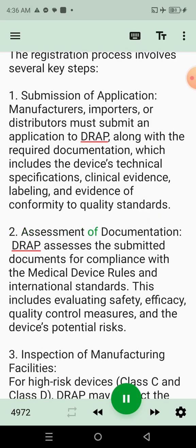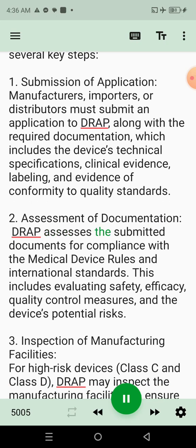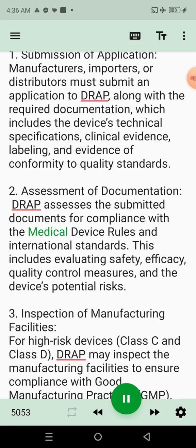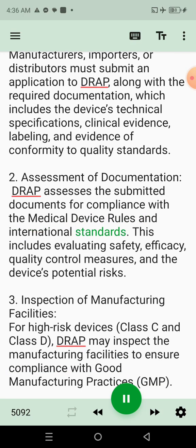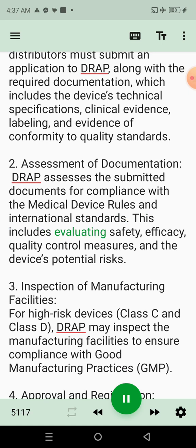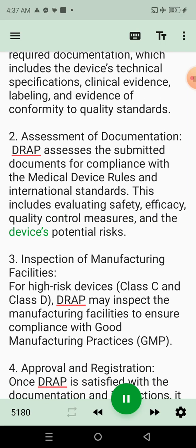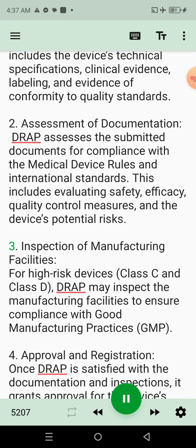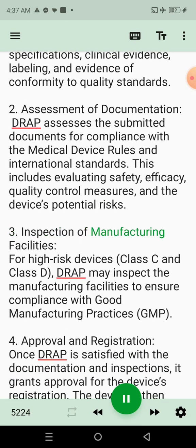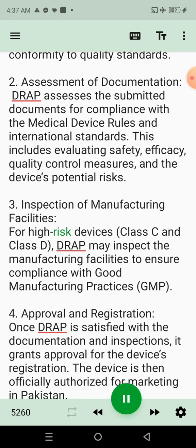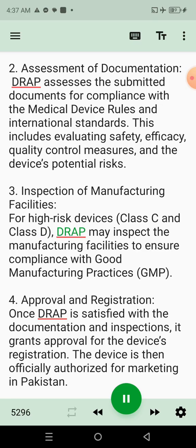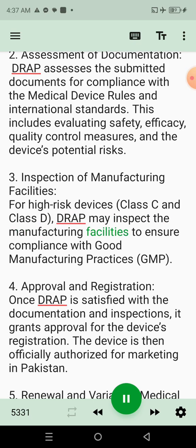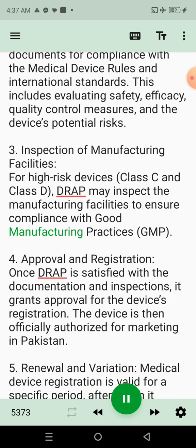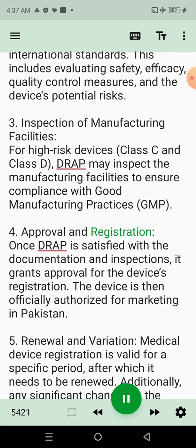2. Assessment of documentation. DRAP assesses the submitted documents for compliance with the medical device rules and international standards. This includes evaluating safety, efficacy, quality control measures, and the device's potential risks. 3. Inspection of manufacturing facilities. For high-risk devices (Class C and Class D), DRAP may inspect the manufacturing facilities to ensure compliance with Good Manufacturing Practices (GMP). 4. Approval and registration.